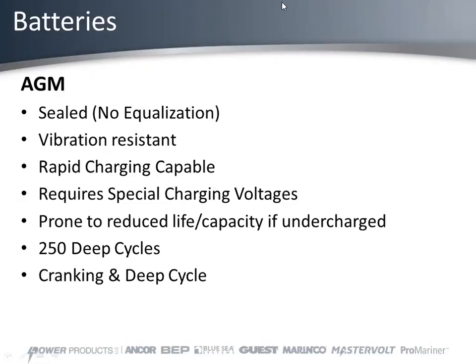Average is about 250 cycles. Do you guys know what a cycle is? It's when you go from 100% charged battery down to 0, back to 100%. That's one cycle. From a life perspective, we say don't discharge your battery more than 50%. So going from 100 to 50 and back to 100 is half a cycle; do that twice and that's one cycle. On average it's 250 cycles for an AGM battery, but since customers typically only discharge 50%, they're actually getting 500 cycles out of it.